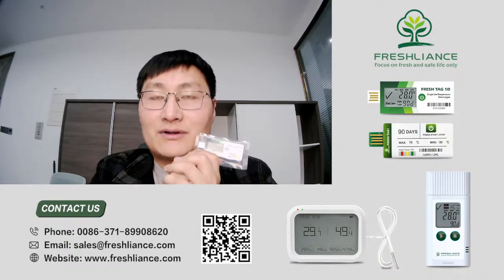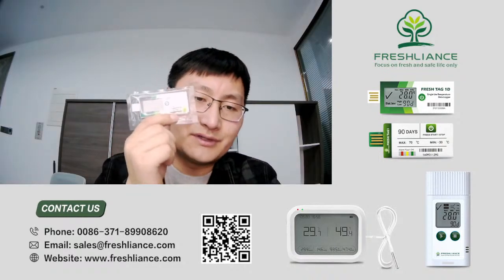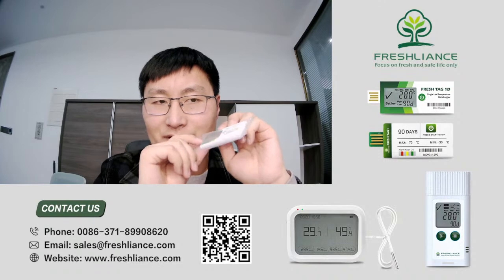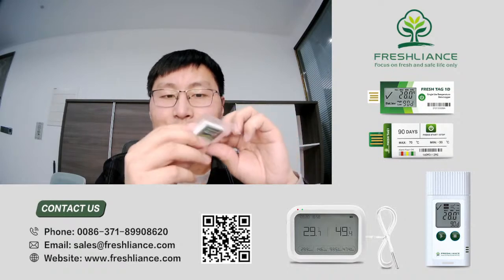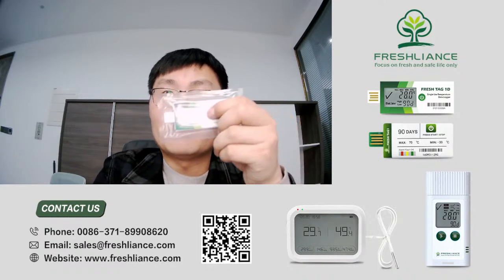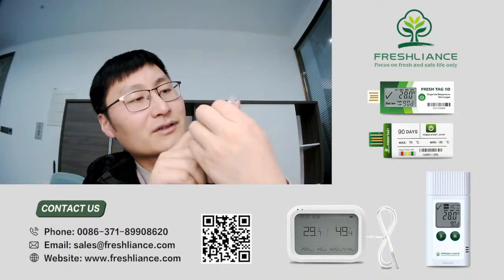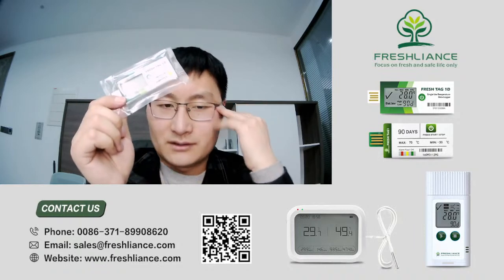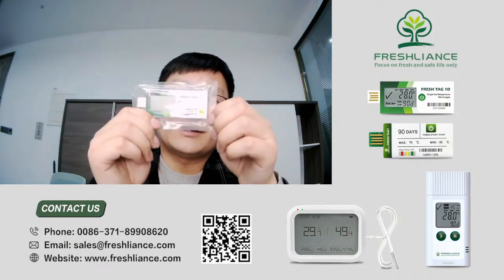So, all of our friends, this is Fresh Tag 1D. It's a single-use temperature data logger. You can see the real-time temperature shown here during working. This device is a used device, so now it cannot check the temperature, but I can see the temperature history of the max value and the minimum value. You can see max 28.4 and minimum 27.7. This is the previous data of this device.